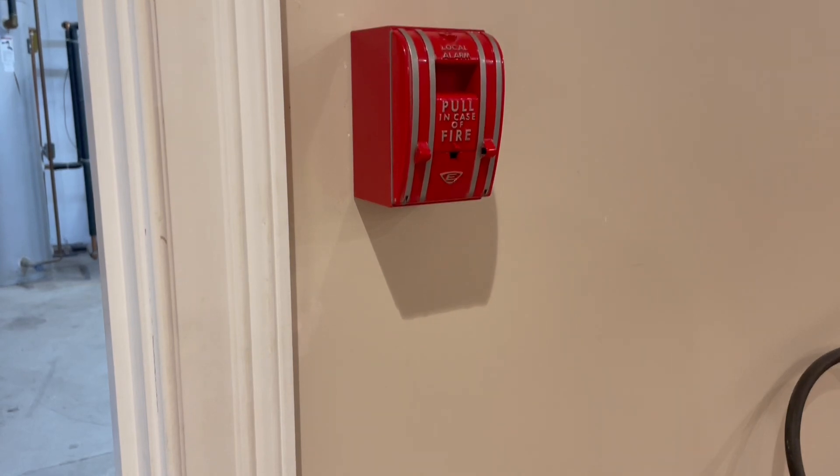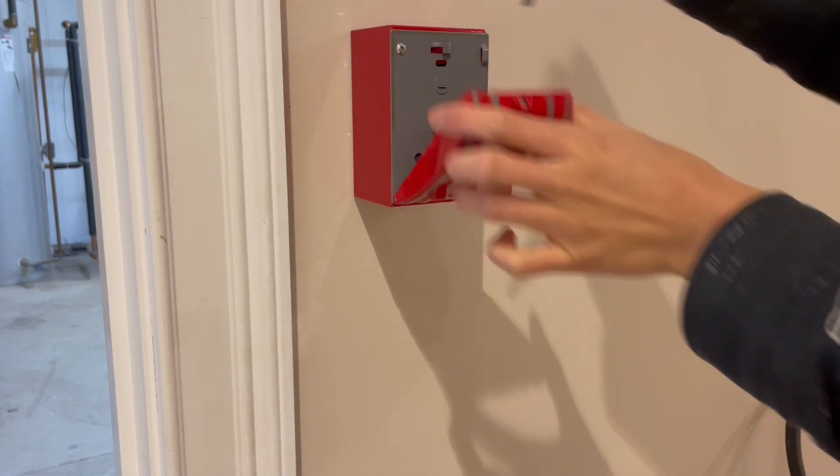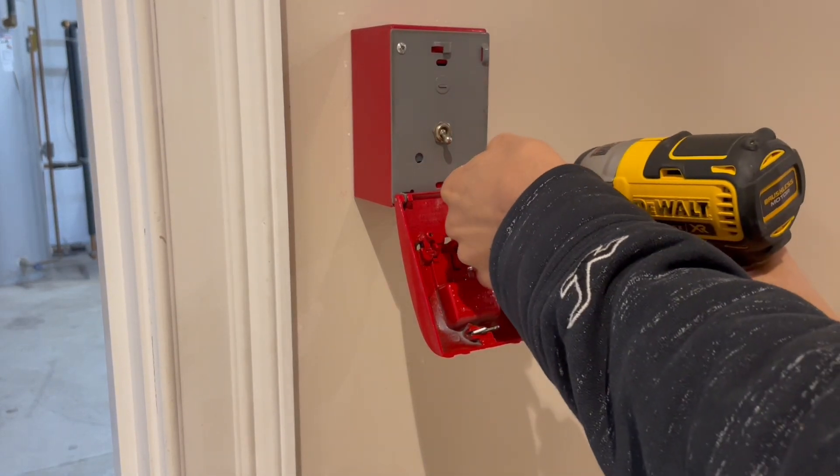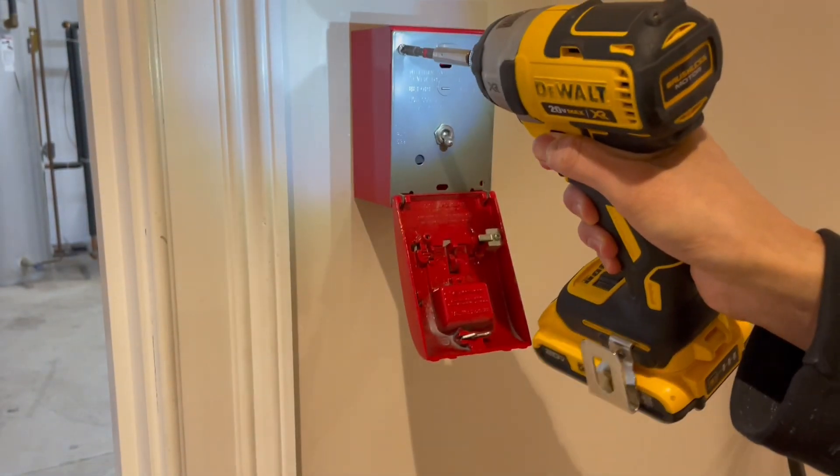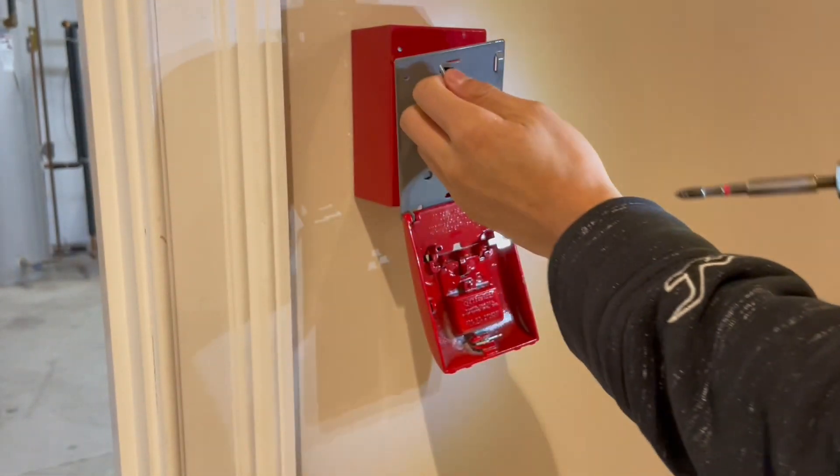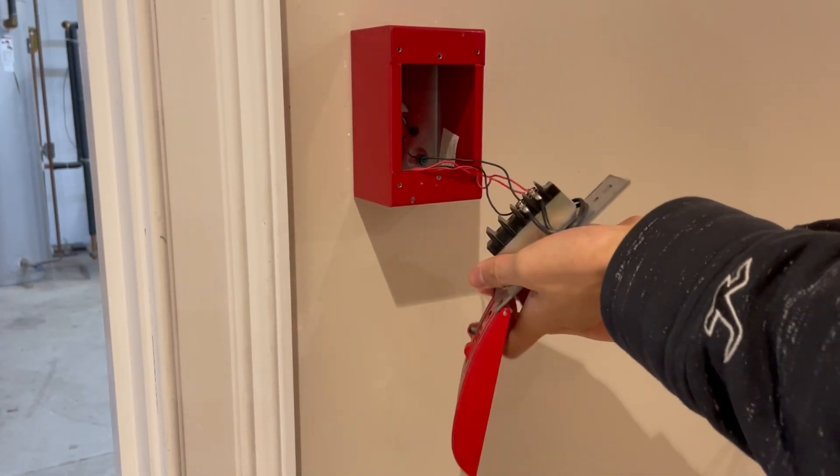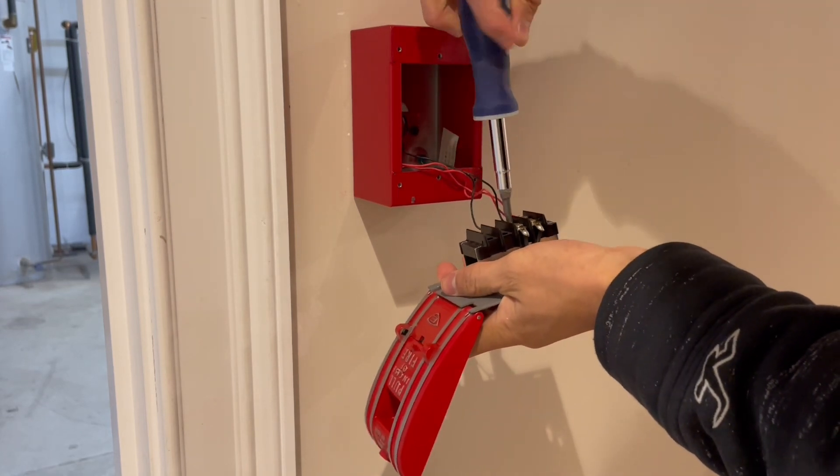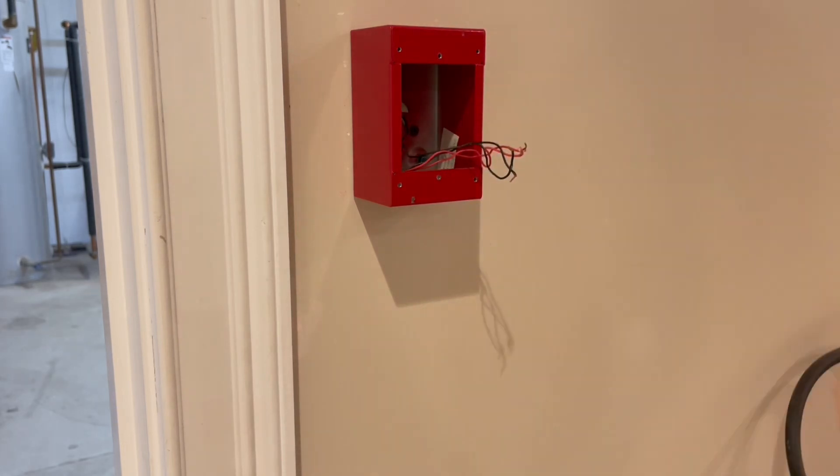Now I'm going to replace this pull station. You open it at the top with a small flathead screwdriver. Just turn it counterclockwise, and then there's two screws like pretty much every other device. So I'll just remove those, and that exposes the wires behind the device. So you just pull it out like this. You can take your flathead screwdriver once again and release these terminals like so. Pull that out, and there you go.